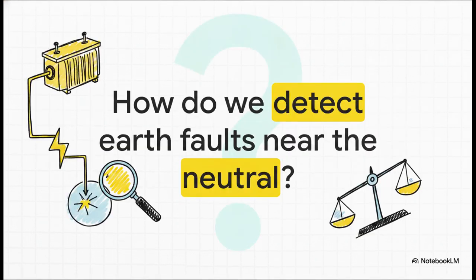So, we have successfully protected our main phase lines from internal shorts, but power systems are incredibly complex, and this differential scheme actually has a tiny blind spot. What happens when a tiny amount of current leaks to ground right near the neutral line where the voltage is incredibly low? How do we catch an earth fault that the main balance scale might just miss? Well, we need an entirely different type of protection for that, and that is exactly what we will uncover in our next explainer. See you then!